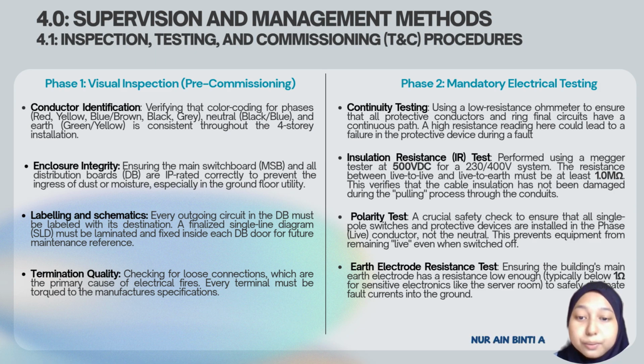Next part is supervision and management method. We have the inspection, testing and commissioning, or T&C, procedure. The T&C phase is the most critical quality control mechanism in the building life cycle. It ensures that the theoretical design from proposal A or B has been translated into a safe physical reality that complies with the Electricity Regulation 1994 and MS IEC 60364. So we have three phases.